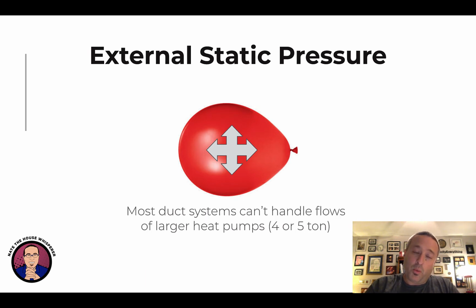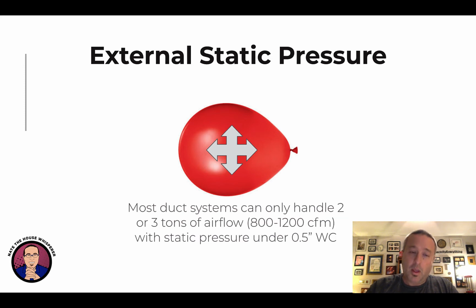So, and this brings up a really key thing. We talk a lot about reducing the load in a house so that it can be heated by a 2 or a 3 ton heat pump, which is 24,000 or 36,000 BTUs. And if anybody from the EU is watching this, 36,000 BTUs is about 9.5 kW. So a lot of houses may need a 4 or a 5 ton heat pump to really do them well in a cold climate if they're leaky. But most duct systems just can't do that. So you're going to toast that HVAC system really quickly. Most duct systems can really only handle 2 or 3 tons, which is why we work hard to reduce the load of our advanced project homes into that range so that we can put a heat pump in and everything's hunky-dory.